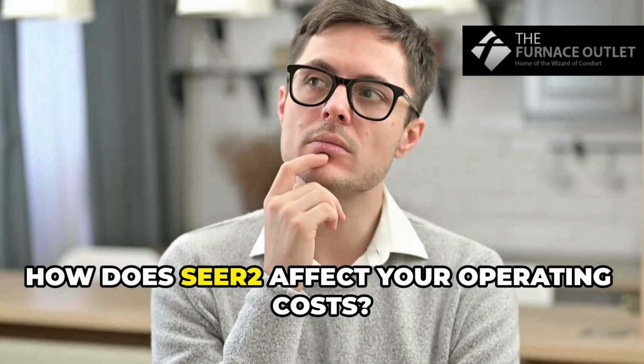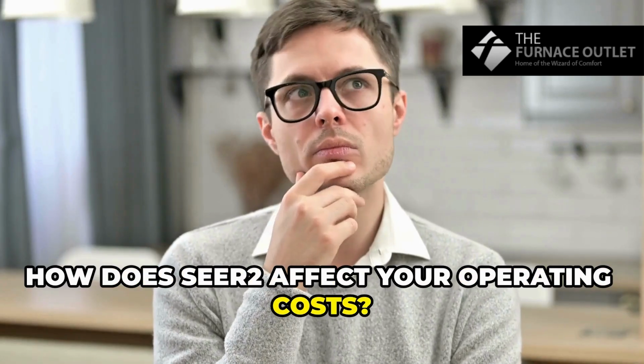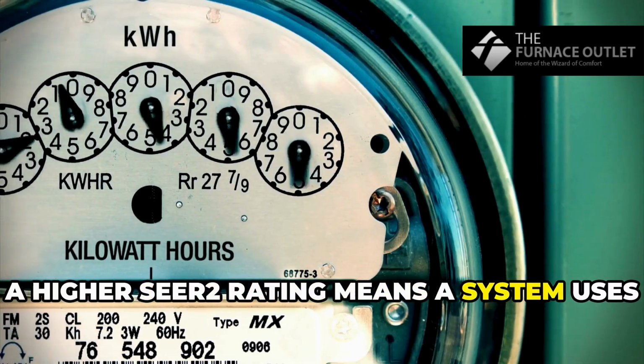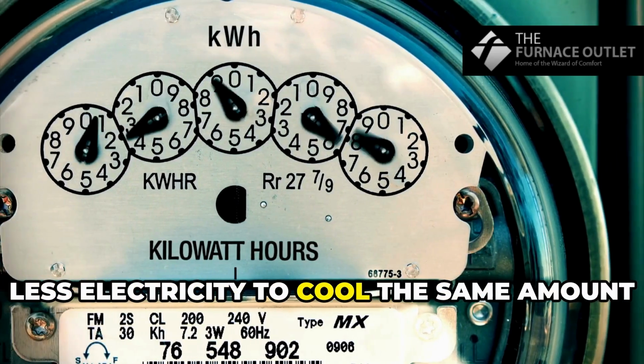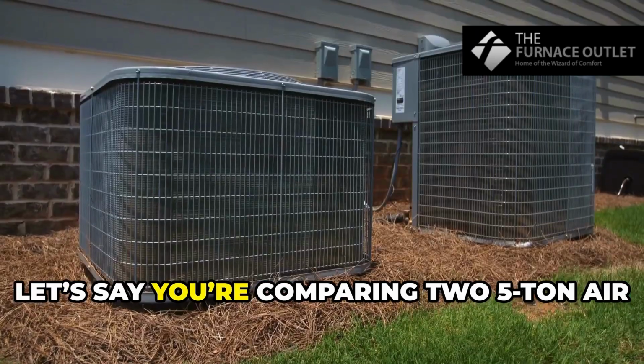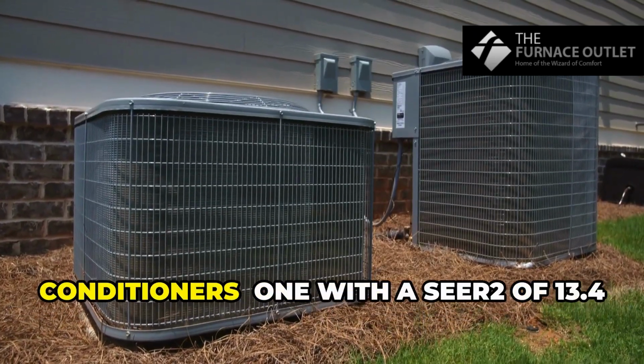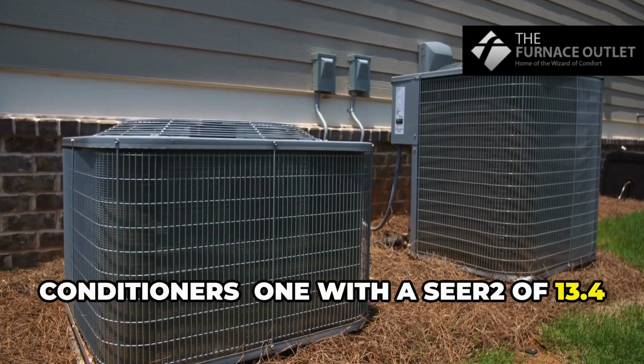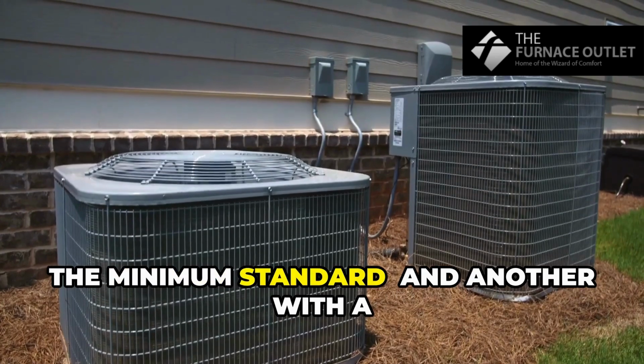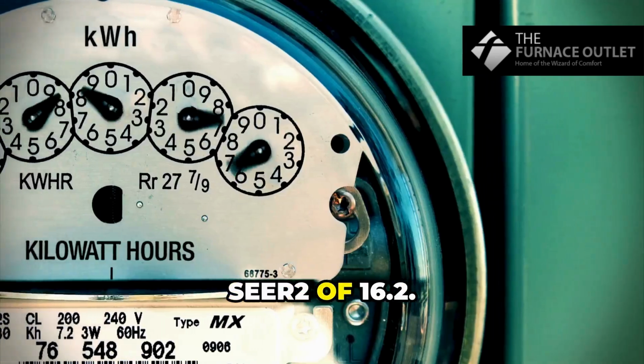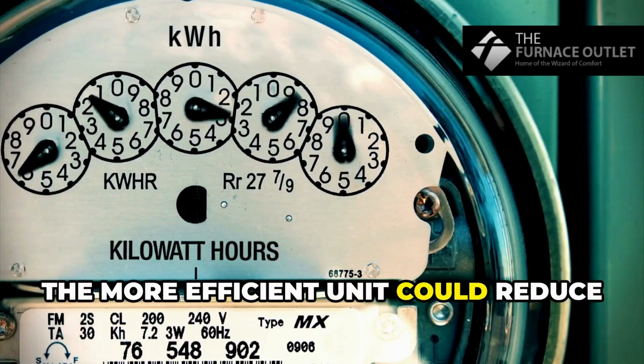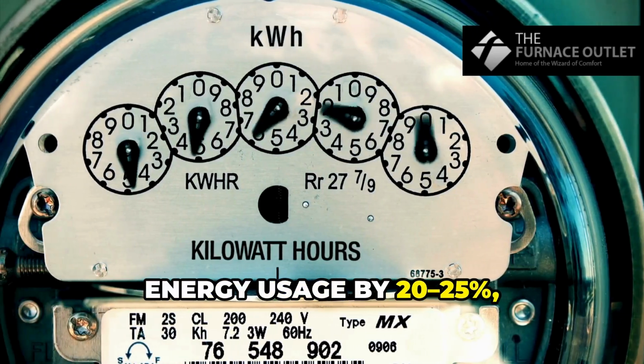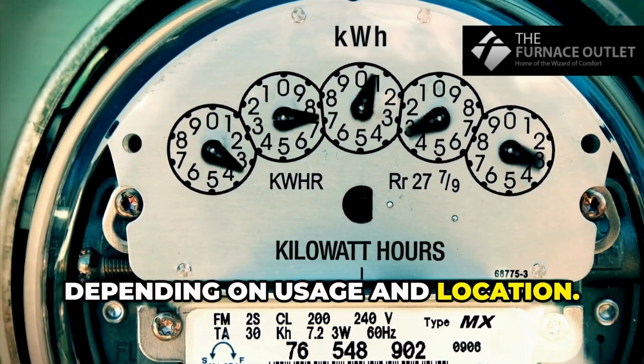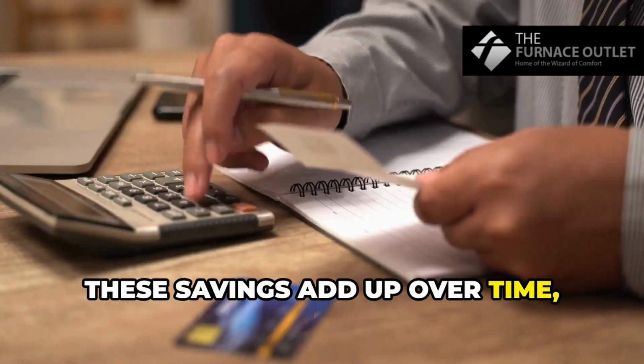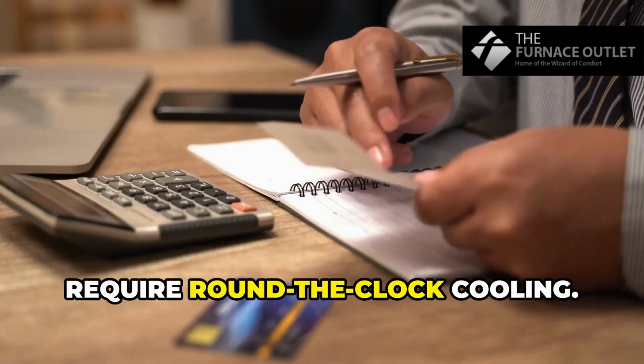How does SEER2 affect your operating costs? A higher SEER2 rating means a system uses less electricity to cool the same amount of space. Let's say you're comparing two 5-ton air conditioners, one with a SEER2 of 13.4, the minimum standard, and another with a SEER2 of 16.2. The more efficient unit could reduce energy usage by 20–25%, depending on usage and location. These savings add up over time, especially in commercial buildings that require round-the-clock cooling.